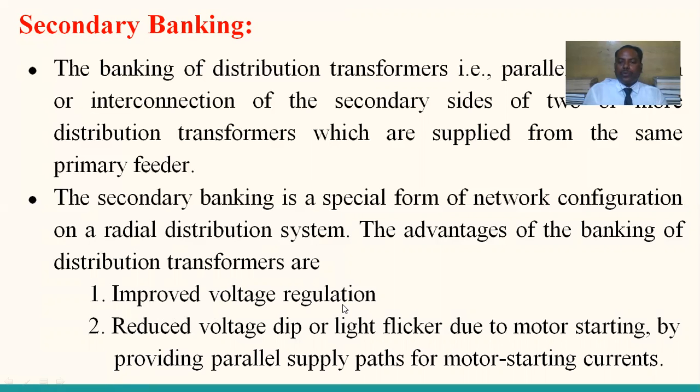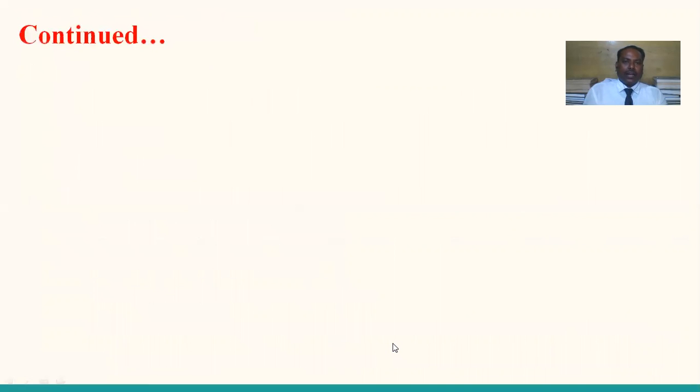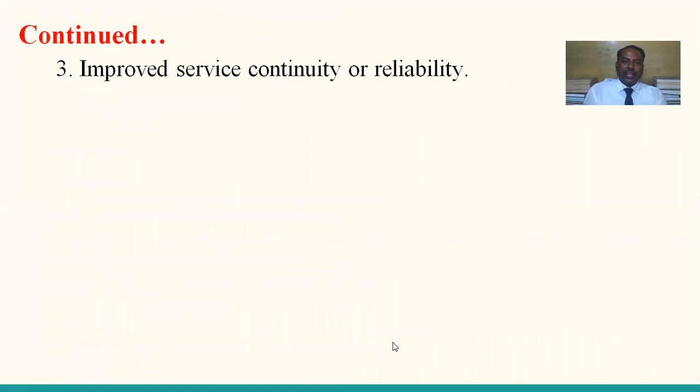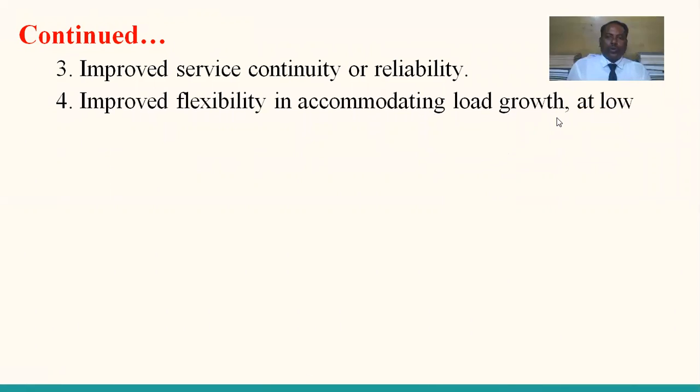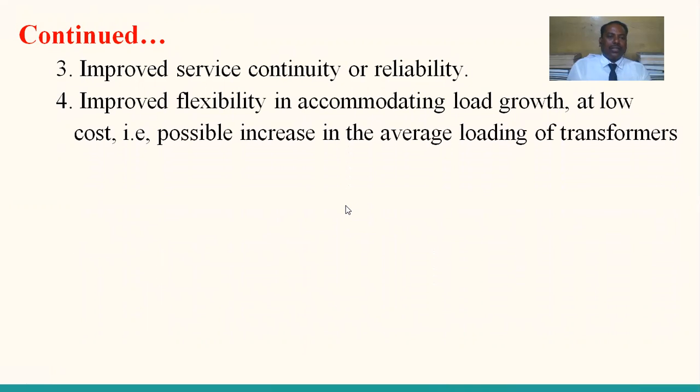Therefore, improved voltage regulation and reduced voltage dip or light flicker due to motor starting by providing parallel supply paths for motor starting current, and also improved service continuity or reliability. That may also be used for spare. Yes, service continuity or reliability is possible, and improved flexibility in accommodating load growth at low cost. That means once you keep another transformer with the existing transformer, the load growth may increase drastically. Also, there is no problem.